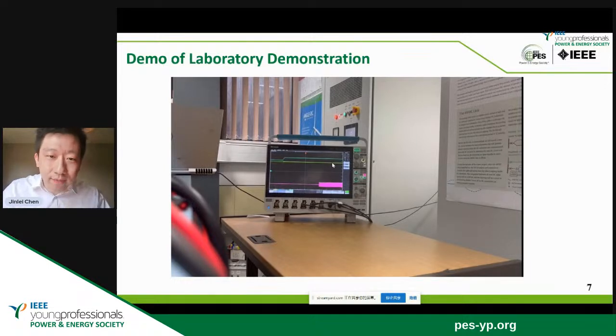Only one converter station is enabled, so it's operated in StatCom operation. So only the reactive power is shown here. We gave different set points of the reactive power, so it can change and trace our given reference. In the end, we disable the power and it decreased to 0.